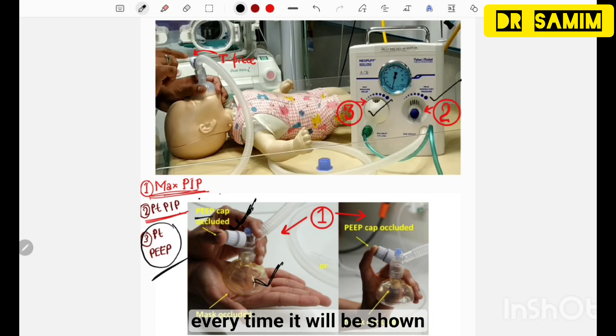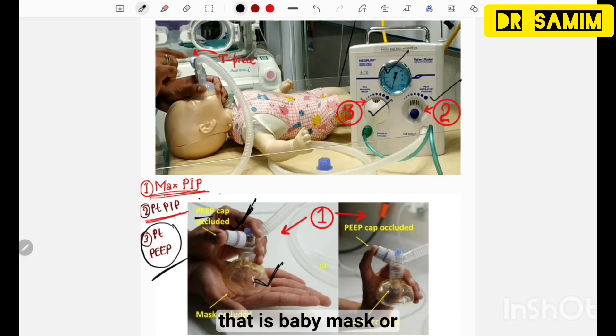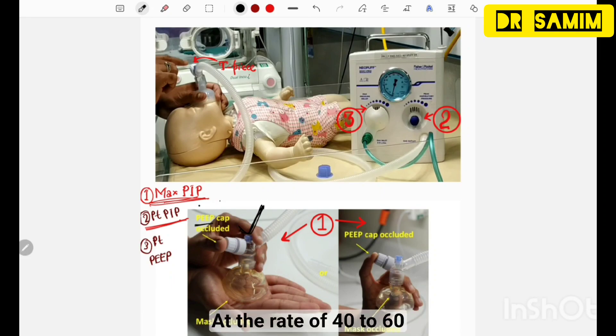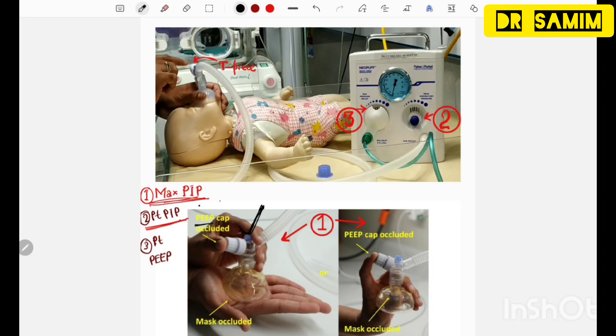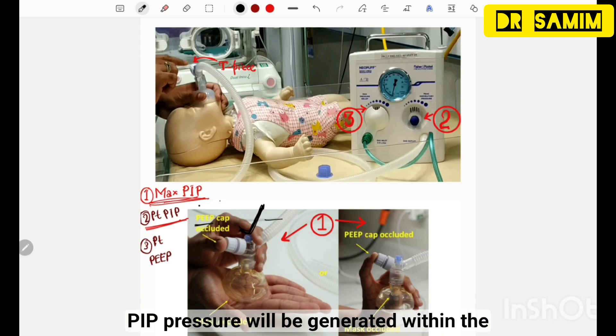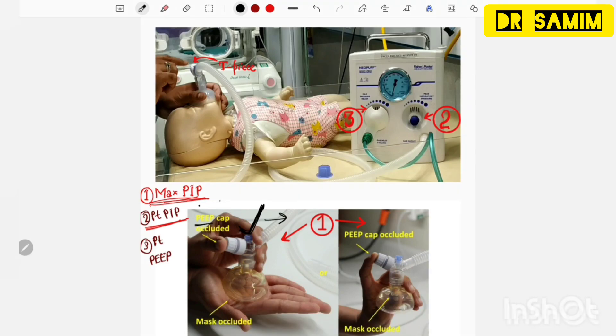When adjusting any pressure, the reading will be shown on the pressure dial. After attaching the patient interface — baby mask or ET tube — to the baby, intermittently occlude the PEEP cap at a rate of 40 to 60 breaths per minute, just like giving breaths to the baby. When the PEEP cap is occluded, PIP pressure is generated; when released, PEEP pressure is generated. The TPS resuscitator can be used in the delivery room for neonatal resuscitation or as transport ventilation when moving the baby from the delivery room to the NICU.